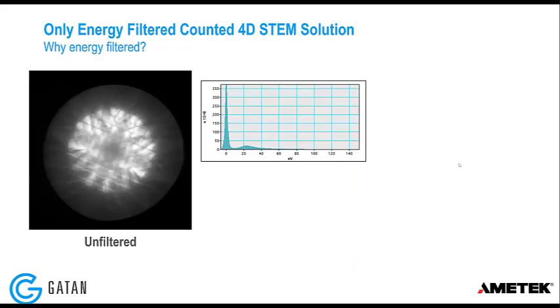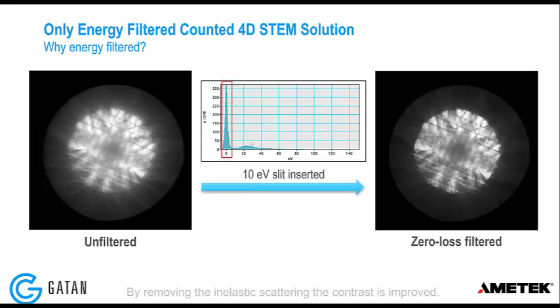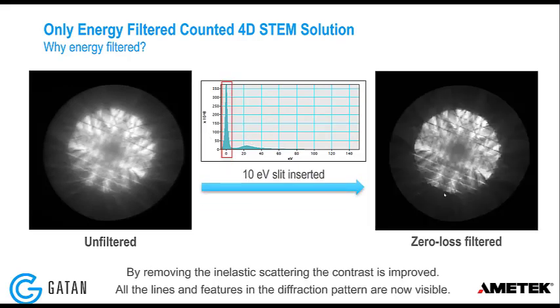A couple of questions arose about whether the K3 camera is installed on a Gatan imaging filter. What you saw today was a pre-GIF camera. But if you have a K3 on an imaging filter, you can apply a zero-loss filter to the diffraction pattern, which gives higher signal-to-noise ratio and better feature definition in the CBED pattern, resulting in higher quality diffraction patterns and better experimental results.